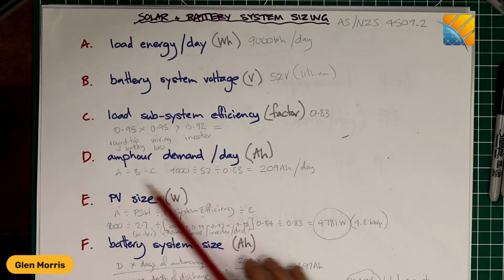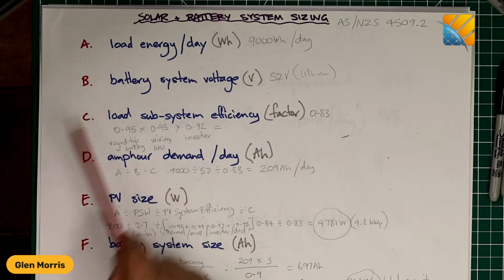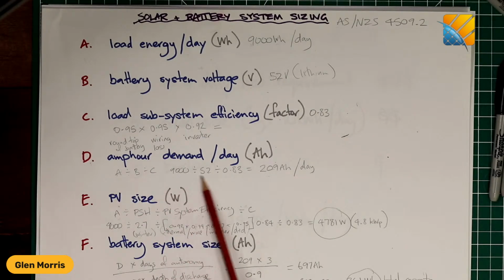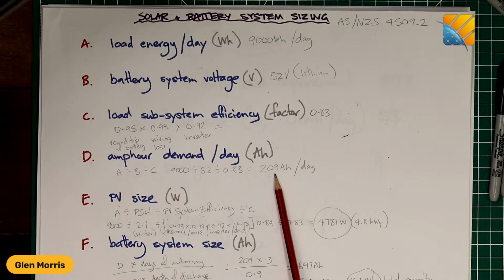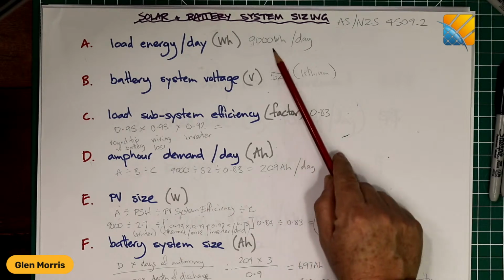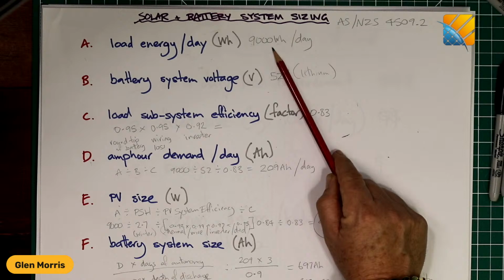Amp hour demand is really just how many amp hours per day will you demand from your battery system. So that's just A divided by B divided by C. A divided by B, and so on, gives me, in this case, a worked example of 209 amp hours per day that I'm going to be taking out of my battery system to deliver 9 kilowatt hours per day of energy to the customer's loads.